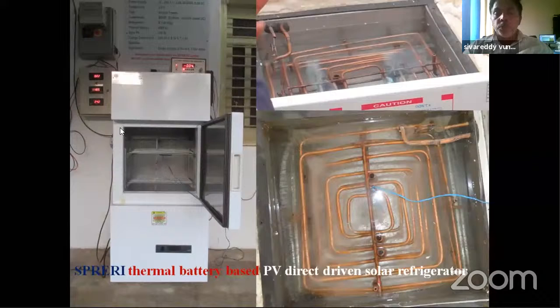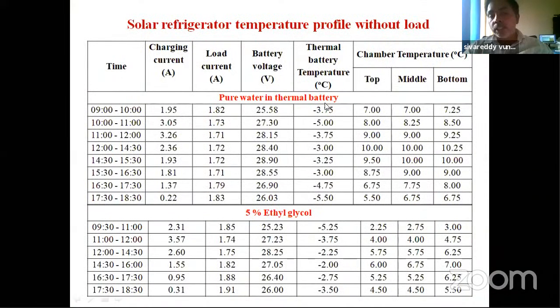But you see, I selected pure water as the thermal storage. Chamber temperatures in the afternoon were reaching greater than 10 degrees. Generally, 4 to 8 degrees is required for vaccines, but it was crossing 10. So for that, we added 5% ethyl glycol. This addition changed the condensation temperature, so automatically the chamber temperatures reduced to less than 8 degrees.